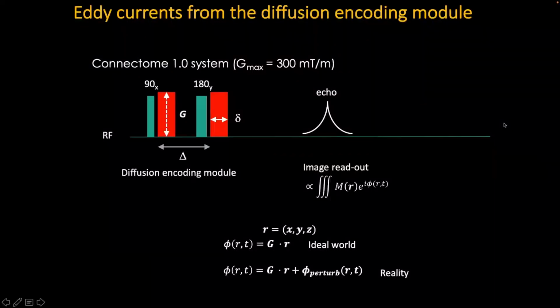Nevertheless, there are some peculiarities with ex vivo diffusion MRI. One is the fact that because the diffusivity of the tissue is reduced, to provide enough diffusion contrast, we have to use much higher b-values than normally used with in vivo acquisitions. So if we want to have high SNR, we have to get a short acquisition time, and the only option is to use gradient systems with ultra high gradient strength, like the Connectome system.